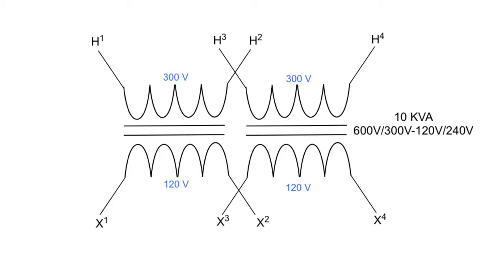Our next step is, we notice that we have a 10 kVA rating here. What we're going to do is split that kVA in half, and that is what each winding can handle as far as kVA output or input is concerned. Therefore, 10 kVA cut in half, that's 5 kVA each winding.